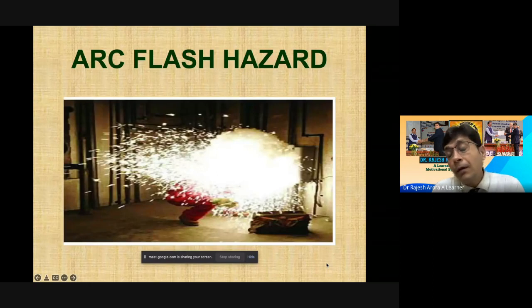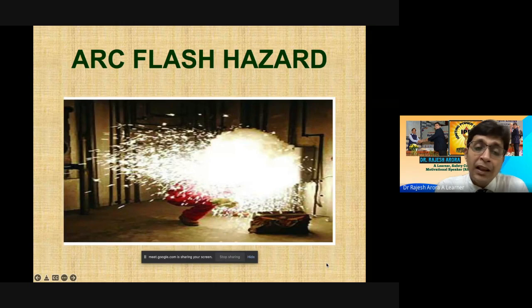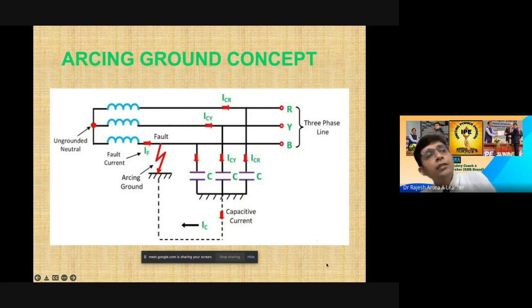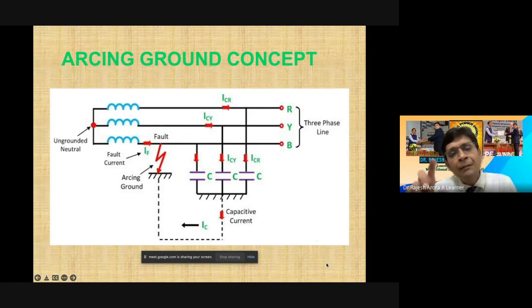We have to be very much careful about the arc flash hazard that may happen, and at the time of that arc flash, the temperature rises up to 19,000 degrees sometimes. That is beyond imagination. Arcing ground usually happens when your system becomes ungrounded. The earth electrode connected to the neutral of your transformer, distribution transformer specifically, gets disconnected from the electrode, and in that case, whenever an SLG, single phase to ground fault happens, the voltage of the healthy phases rises, and that converts into arcing ground, and your gadgets in the healthy phases area become faulty.